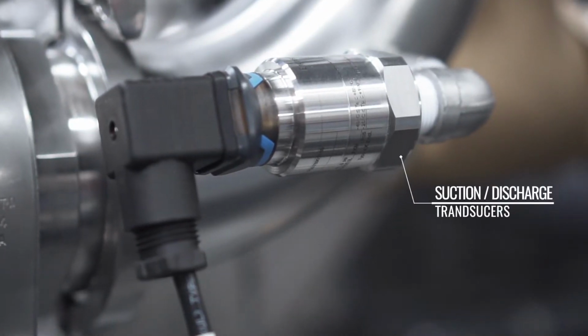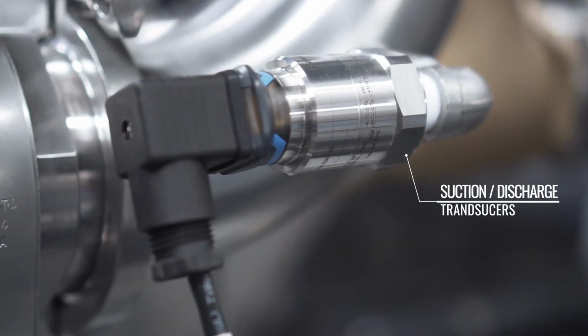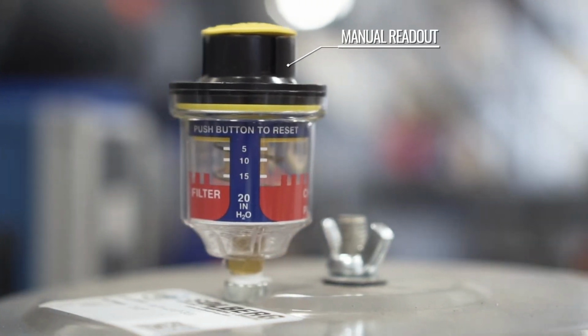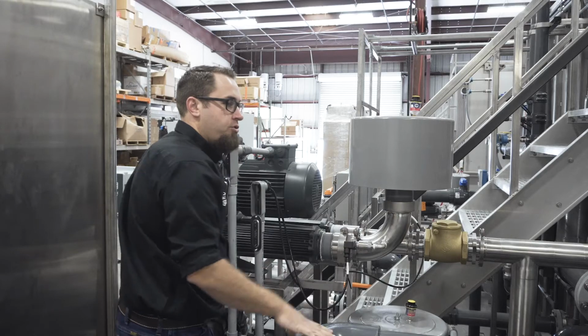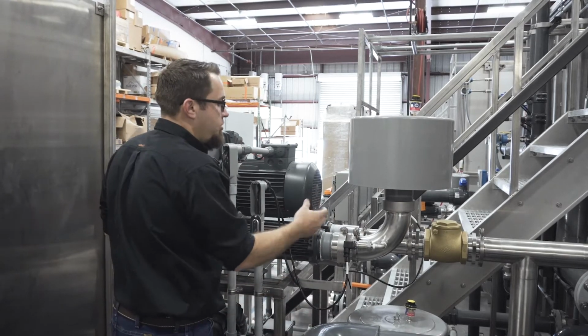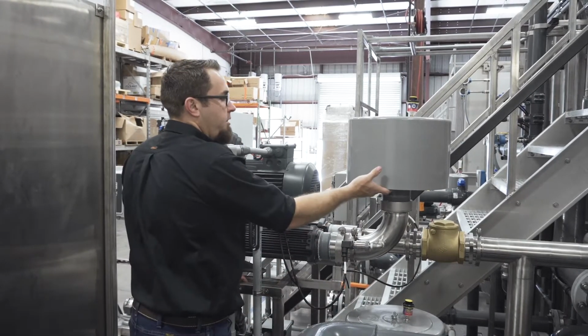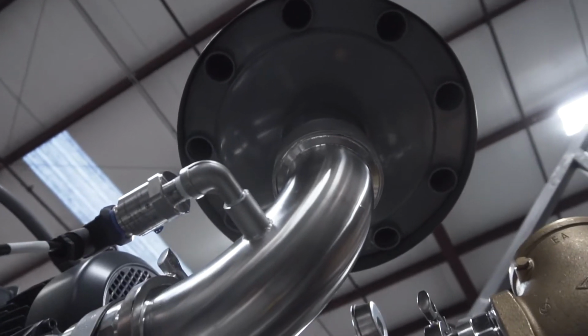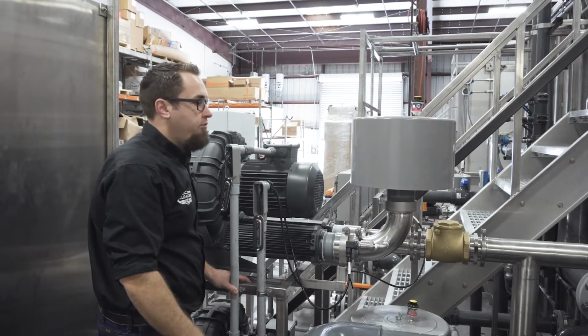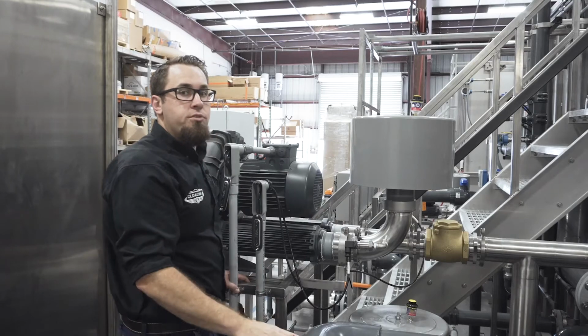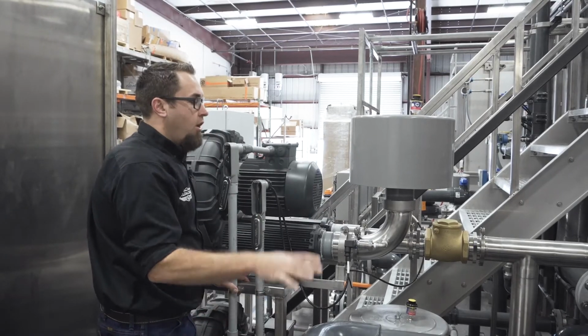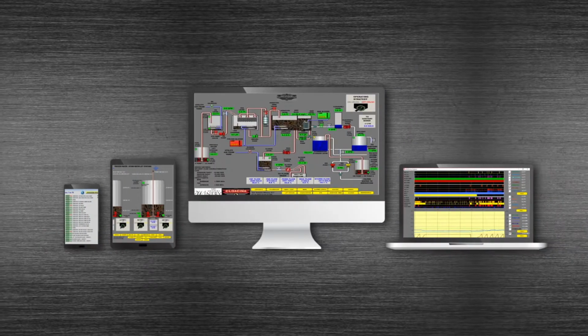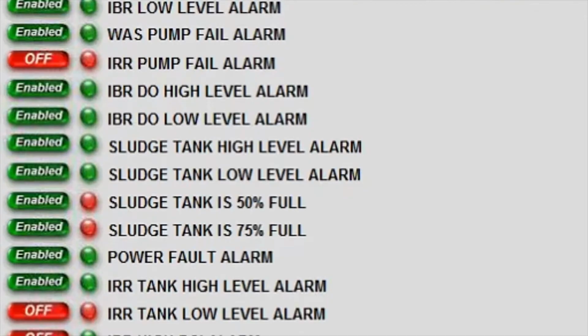We've actually got suction and discharge transducers as well as manual readouts. What this does is it goes back to the control system and tells us if we're having an issue with the blower. Perhaps somebody hasn't cleaned the air filter, maybe something's actually in the blower itself, or perhaps one of the fittings has come loose for whatever reason on the discharge side. All of these things can be troubleshot as a result of having the alarm condition that pops up.